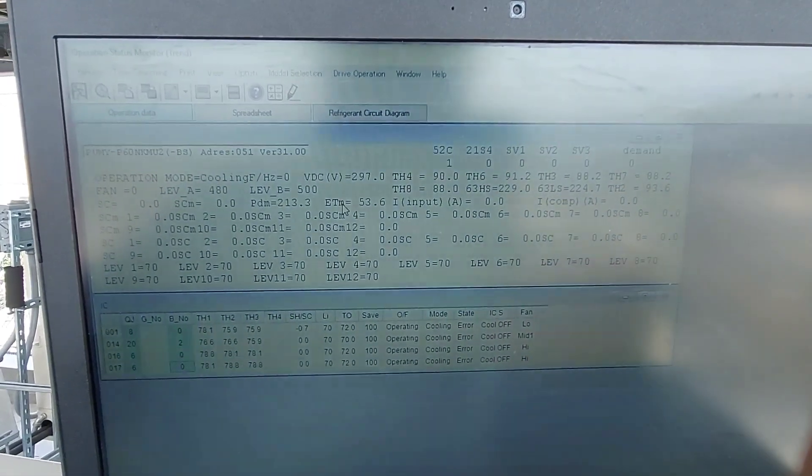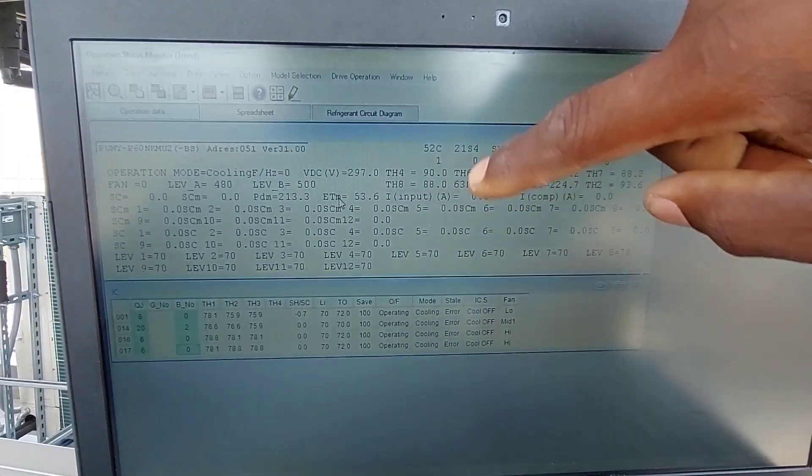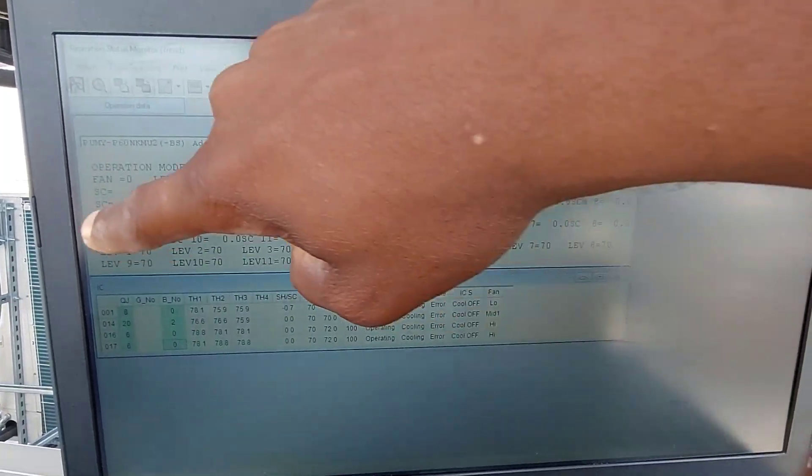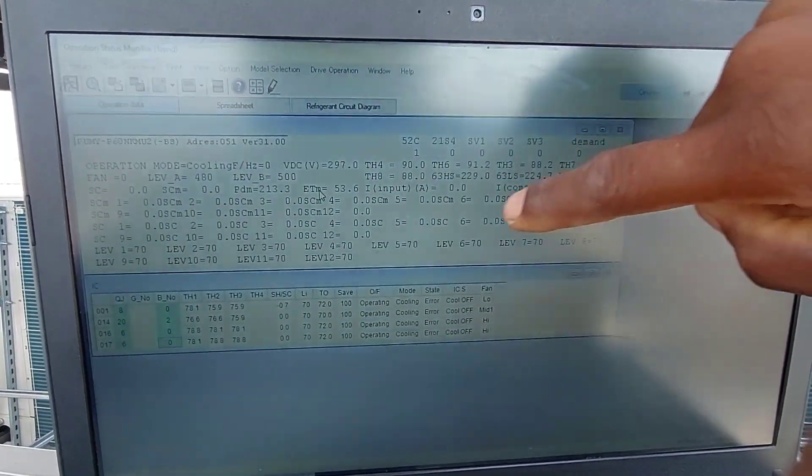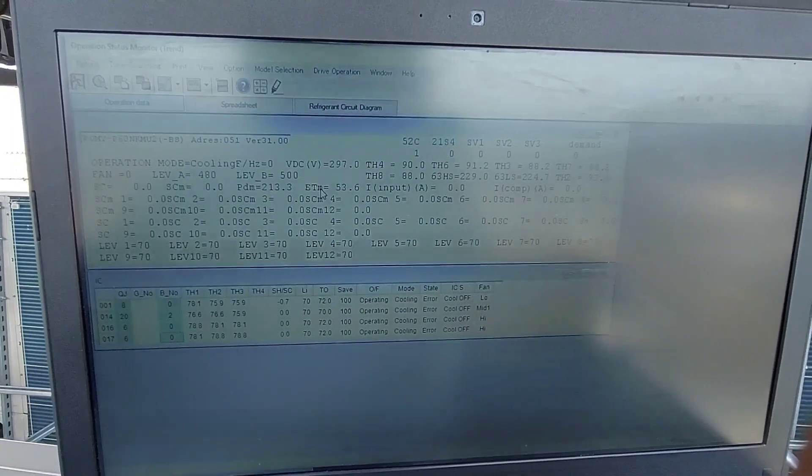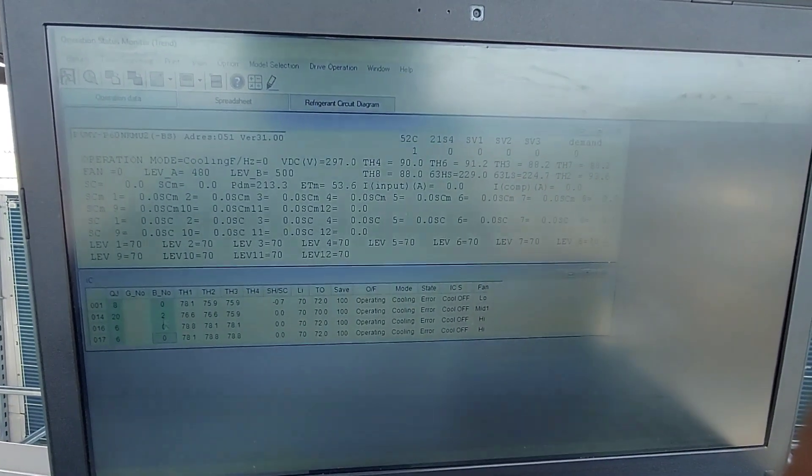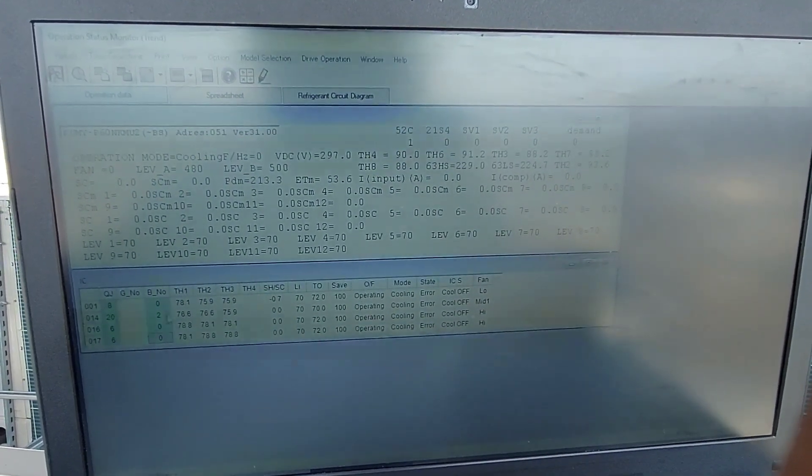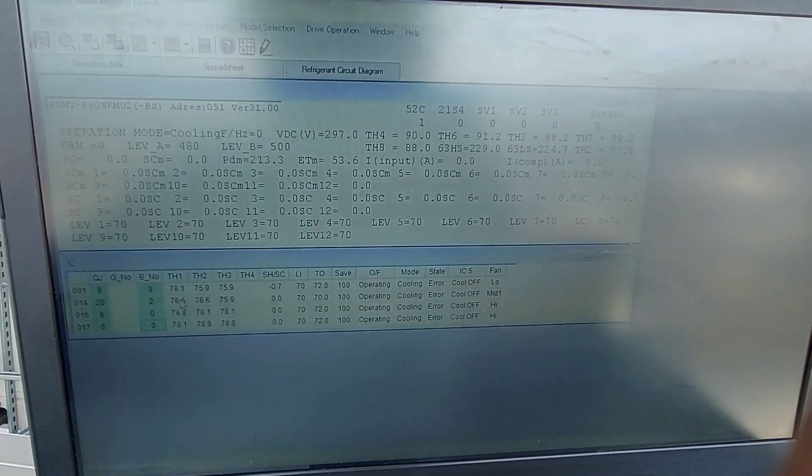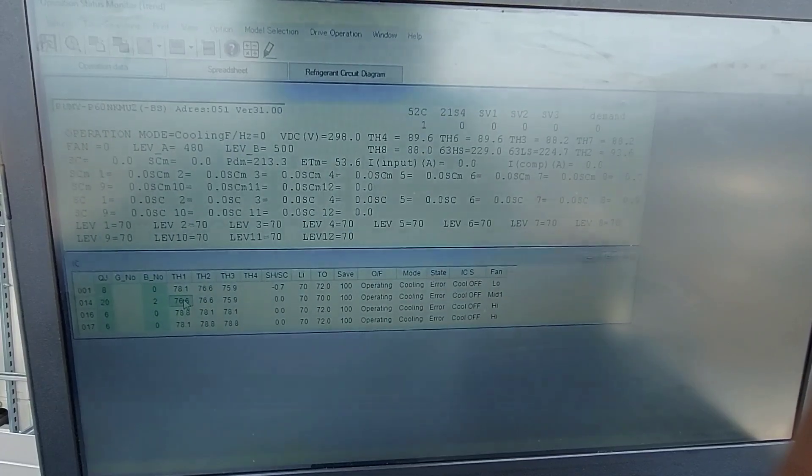This is the outdoor unit right here, this area is outdoor unit section, this is the indoor unit section. There's no branch box, it would have been right here if there is a branch box. So someone messed up with the setting on this one right here on the indoor unit with address number 14, this should have been zero. Whatever, it's not a big deal.